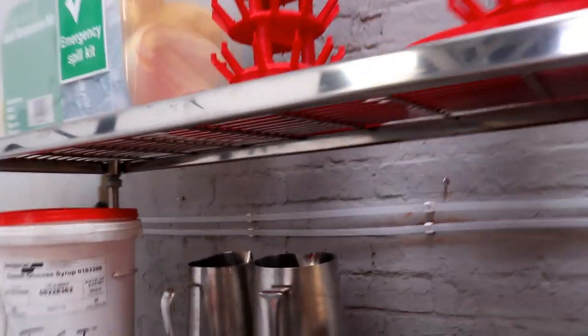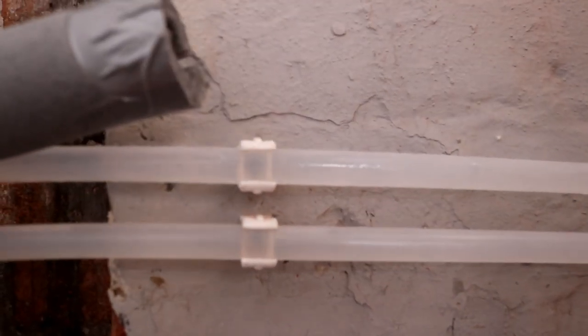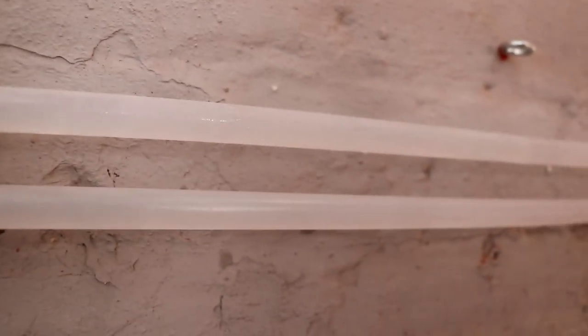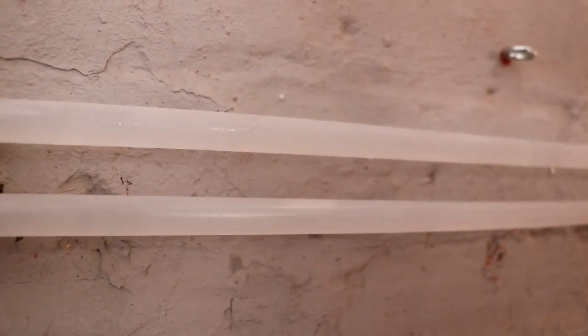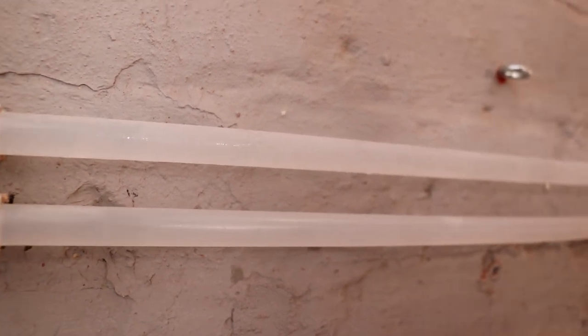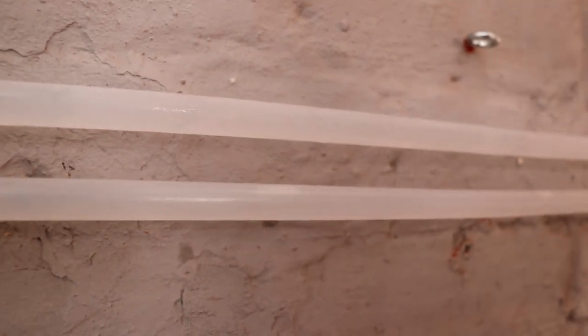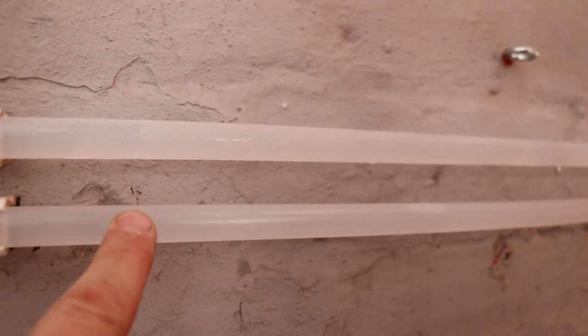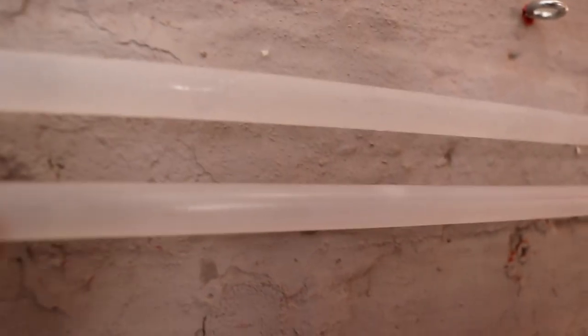So all I have to do now, you can see there's a bubble traveling across there. Look, I don't know if you caught that. There we go. So we know that it's definitely pumping the glycol back to the storage tank. Oh, brilliant. Well, that's good news, because we weren't even seeing any kind of flow like that at all before. And now you can see it. Get in on that pipe. Might be able to see a bubble come by. I think that's the last of them.